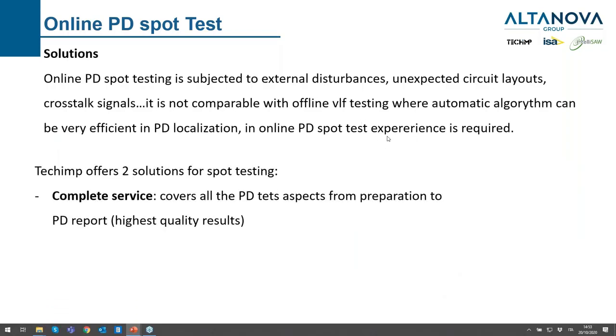In PD spot testing we face external disturbances, unexpected circuit layouts, and crosstalk issues. It's not comparable with offline testing, for example VLF testing, which is very popular right now in medium-voltage cables and is fully automatic — we only have to connect the instrument and the voltage generator together with the detection units. They can efficiently handle localization. In online testing you need some experience.